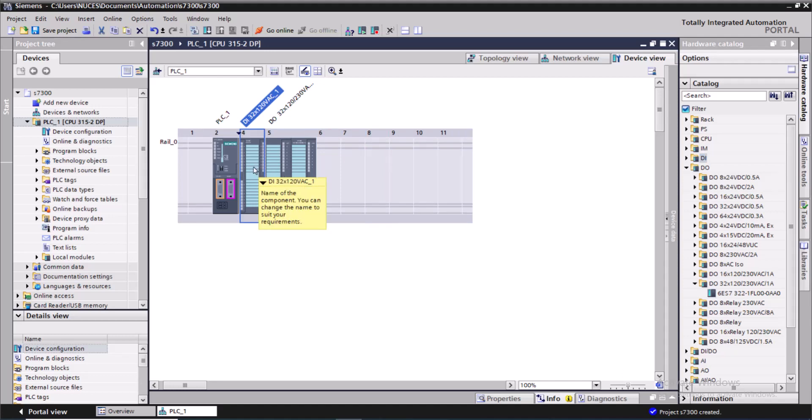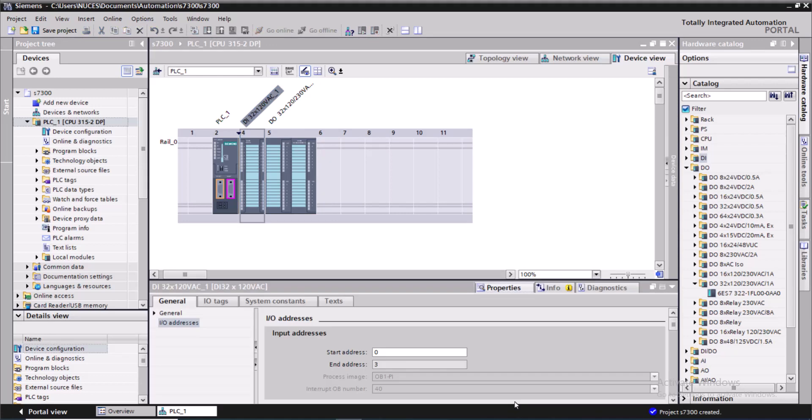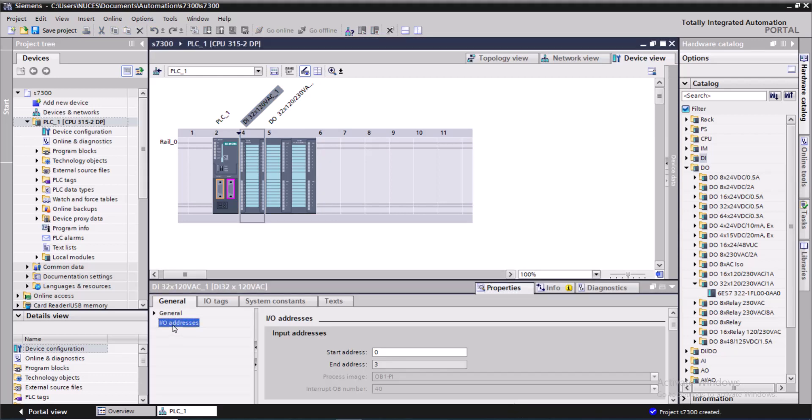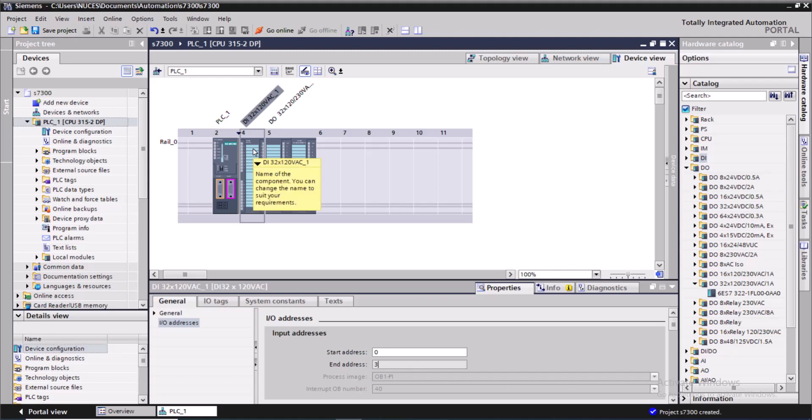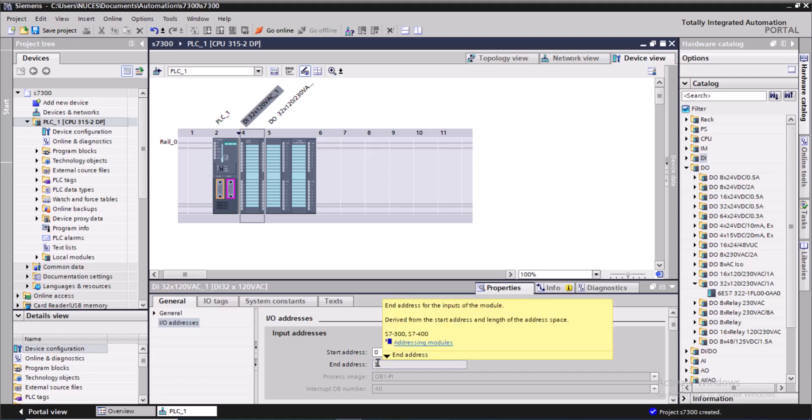If you want to inquire about the addresses of the input and output channels, you can simply click on the card and go to the properties. In the I/O address section, the start address is zero and the end address is three. Since it has 32 channels, the addresses start from I0.0 and will end at I3.7, so that's a total 32-channel card.